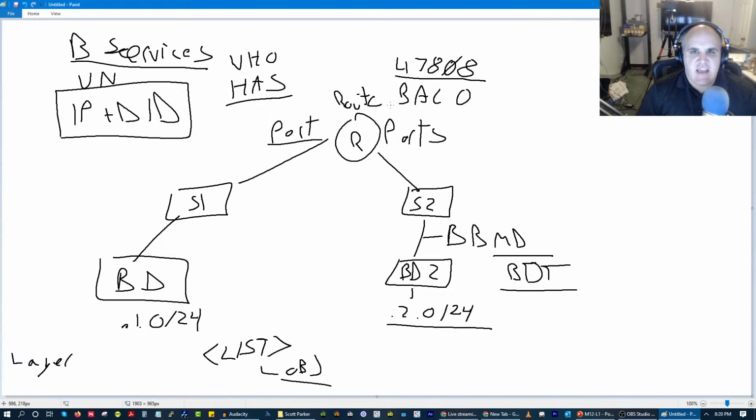The thing is that anyone who tells you BAS traffic is going to bog down your network doesn't know their head from their ass. I mean, they really don't, because if they did, they wouldn't say that. The reality is that BACnet traffic is so light compared to regular AV traffic, big data dump backups, things like that. BACnet traffic is so light and its packet size is tiny. And so BACnet nowadays is not going to do anything.